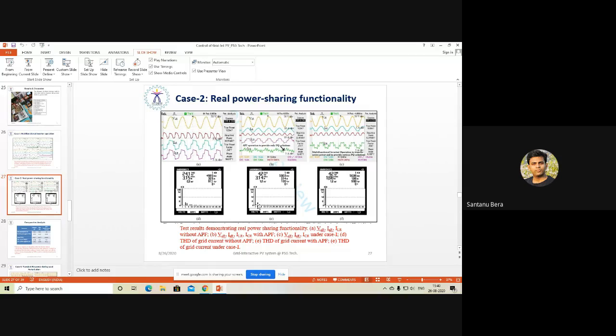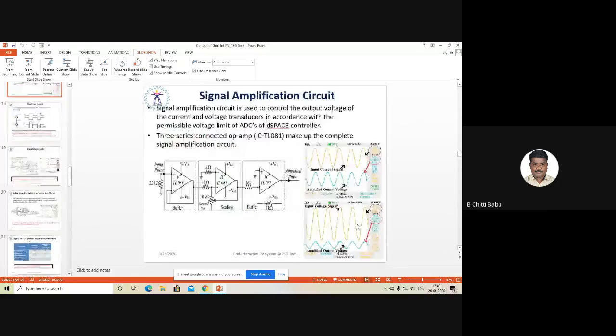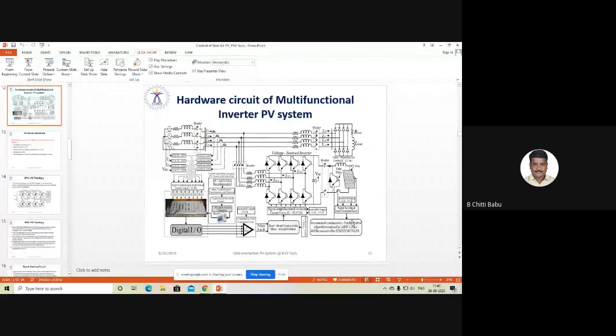Okay, sir, can you please elaborate why the 4-leg is there to utilize the third harmonic? That is not utilized, it is compensating. While you are using the fourth leg, it will provide a path for the neutral current. The fourth leg is basically for the neutral current, and as you are using it, it will provide a path for the neutral. So this will not be interacting with the supply current, so that there is no existence of third harmonic.